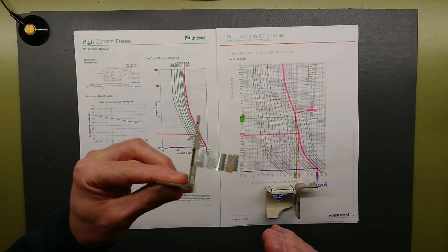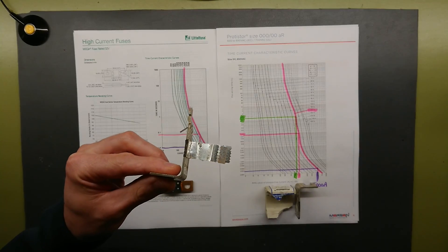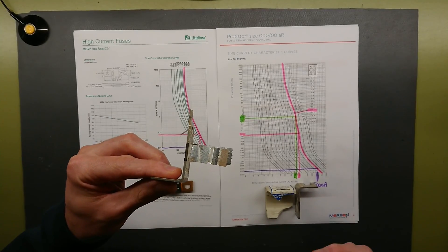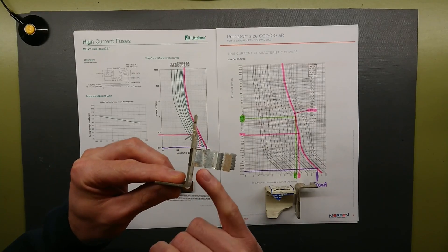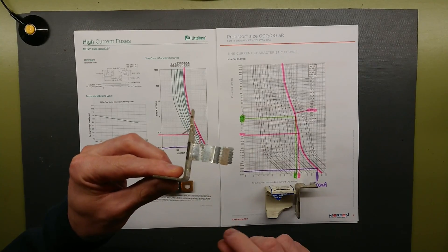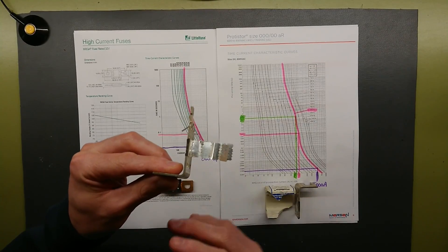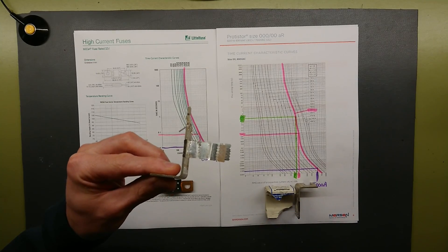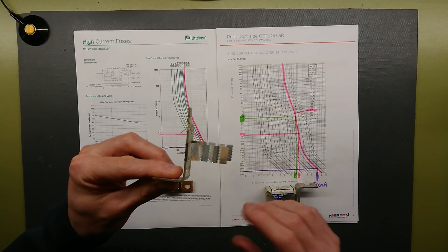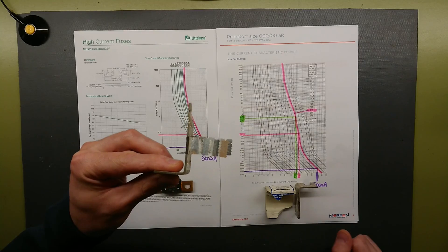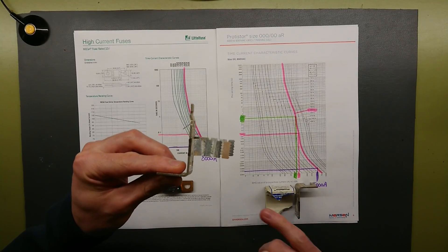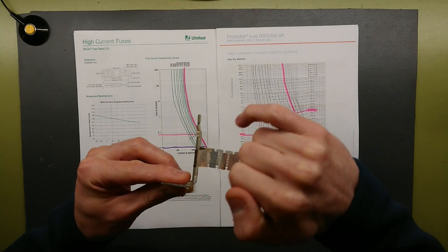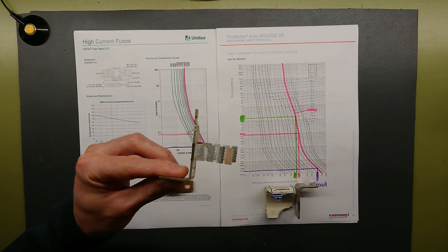This is to give an even break when the fuse melts. Silver has a very even distribution of heat and current. When it breaks all these links will break simultaneously. It also has more sections to isolate the voltage so there is no arc making a connection. The sand will melt at high temperature and insulate between these links.